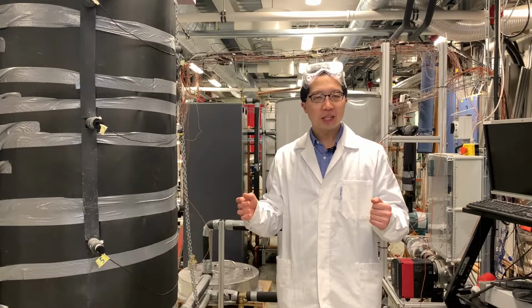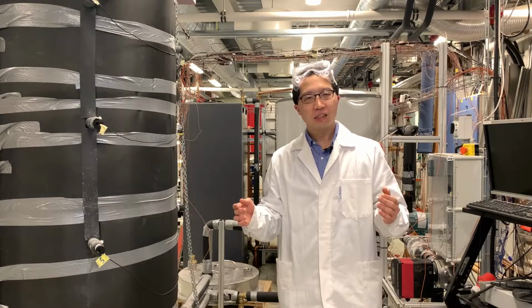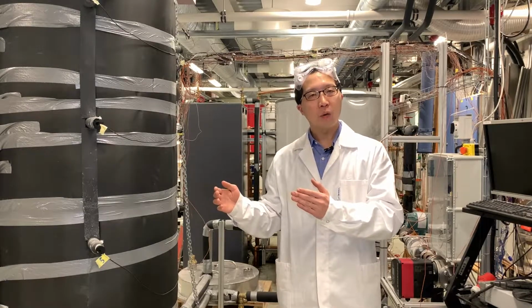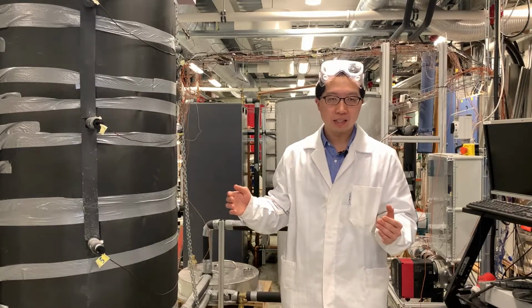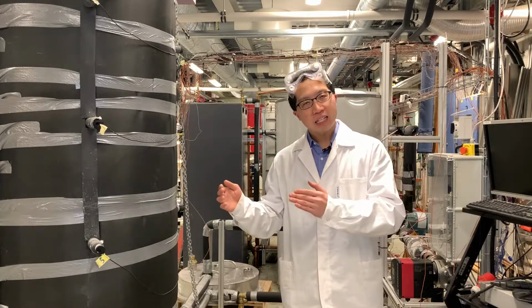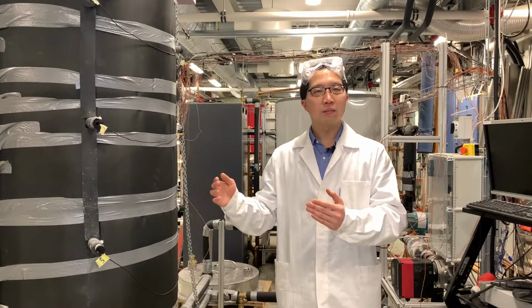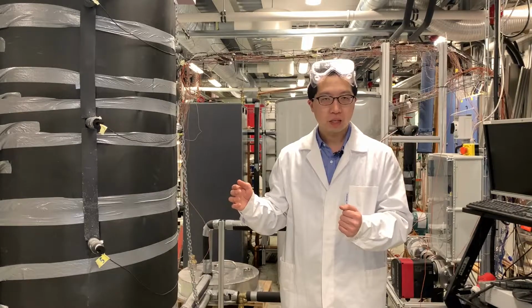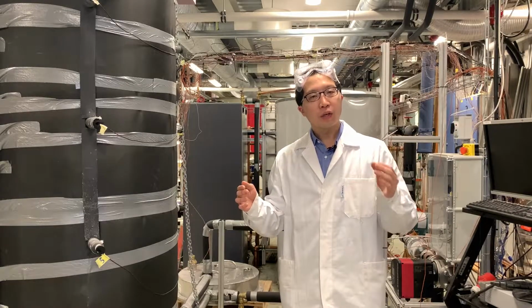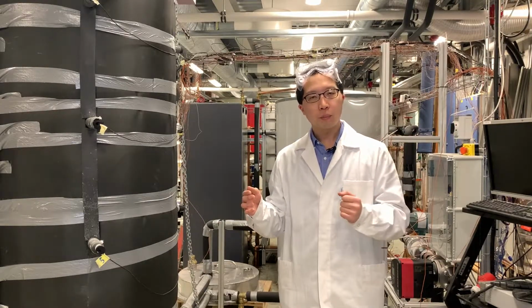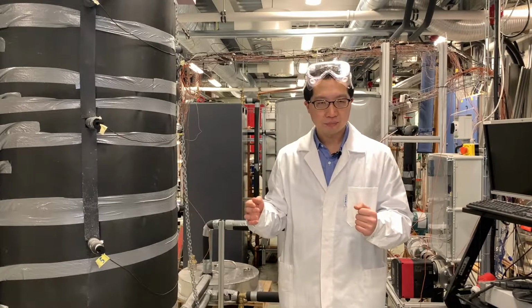We obtain from the different thermal energy storage designs around 60 kilowatt hour per cubic meter of storage capacity. This is 50% higher as compared to sensible hot water storage system. And we obtain around 30 kilowatts per cubic meter of thermal power rating.